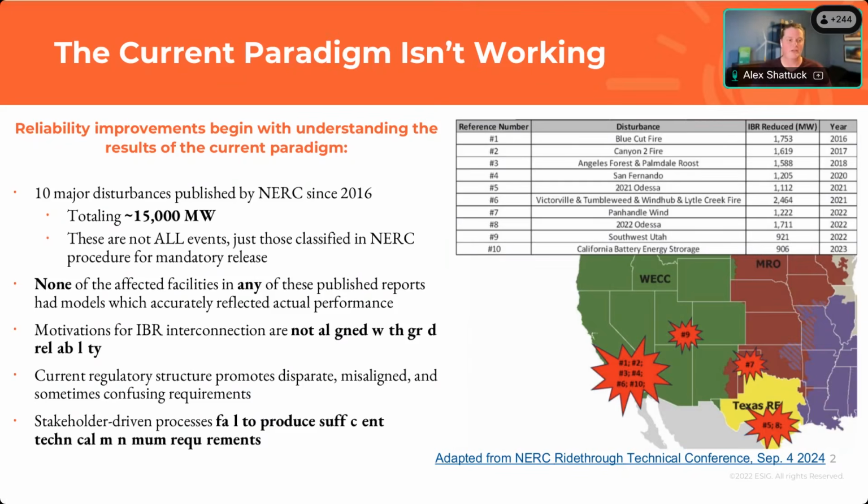During those exercises, in all 10 of these events, in all of the affected facilities, maybe 10 plus per event, so over 100 IBR plants, not a single one of those plants, when we studied their models, had a model that matched how it actually performed, which is, again, a very clear indication that the paradigm isn't working.